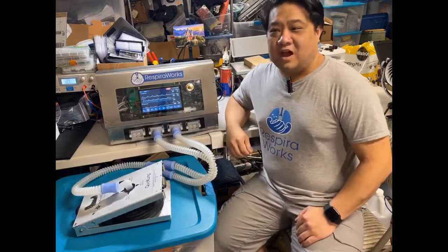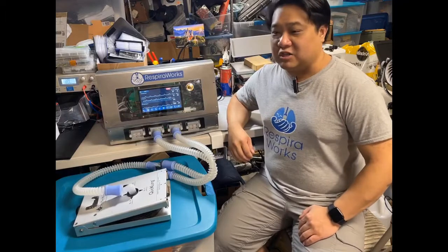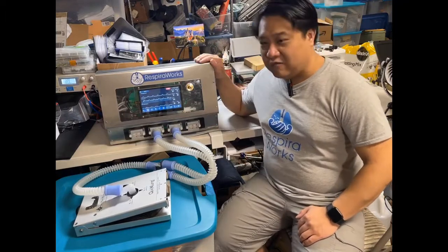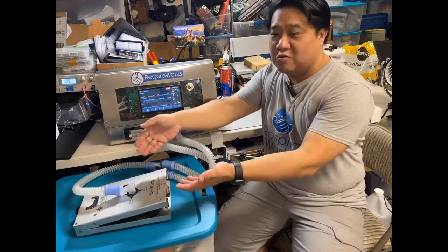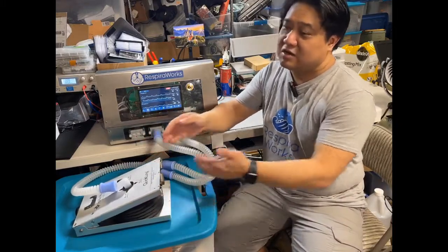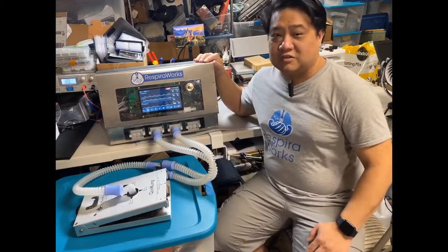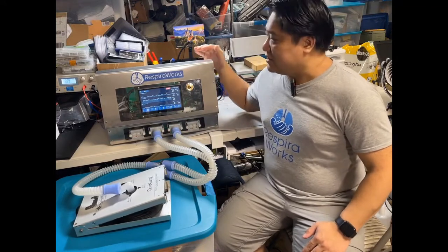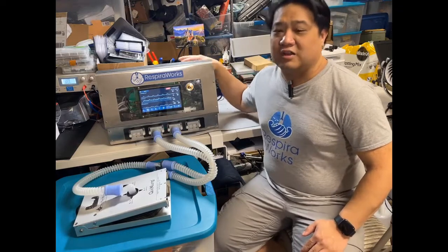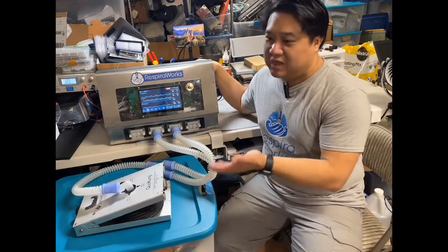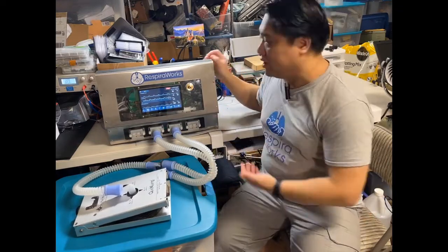Hello, I'm here today at RespiraWorks to give a quick hardware demonstration of our ventilator. Right now, the ventilator is connected to a QuickLung here, which simulates the patient's lungs. Now, if the patient doesn't require supplemental oxygen, this ventilator is blower-based, which means it can run only on electricity, providing the patient with ambient air that it draws in through the blower.